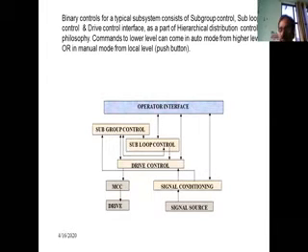MCC is the electrical panel. This 24-volt signal will go to the MCC, and it will give command through the interposing relay to the drive. Then it will take feedback also for protection of the drive.